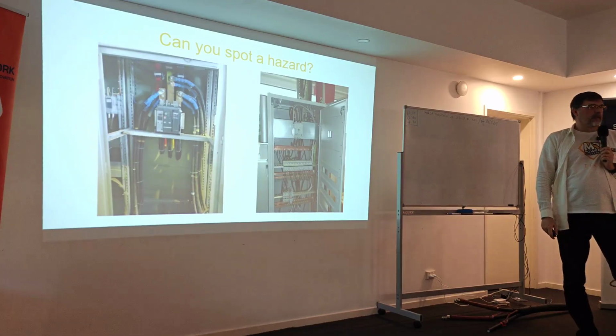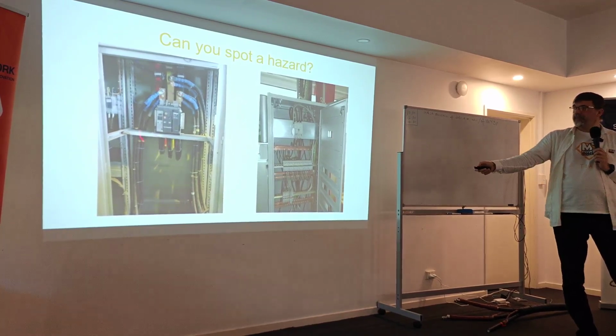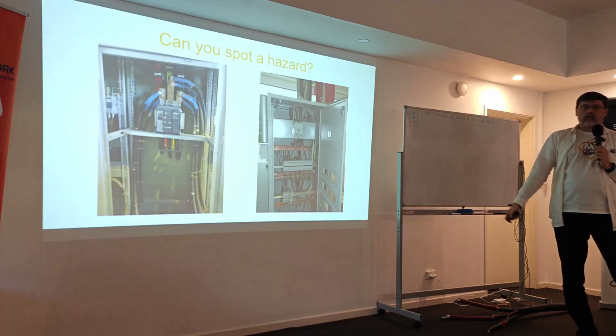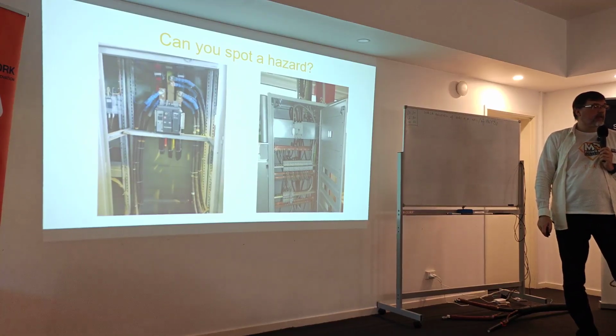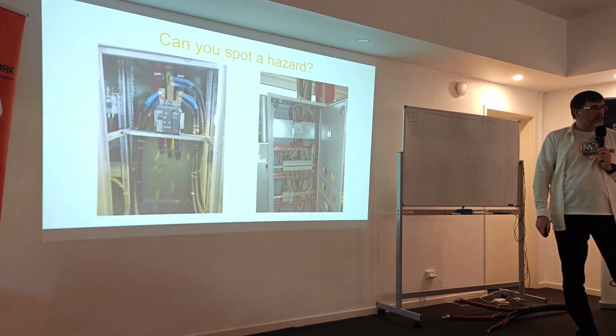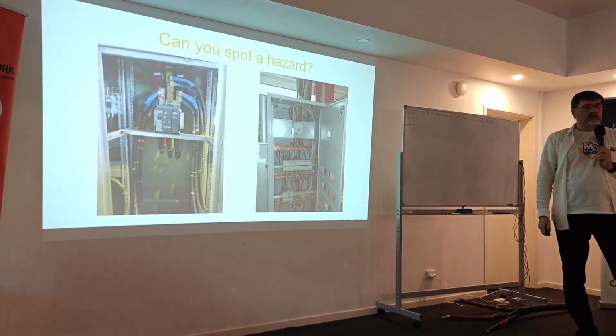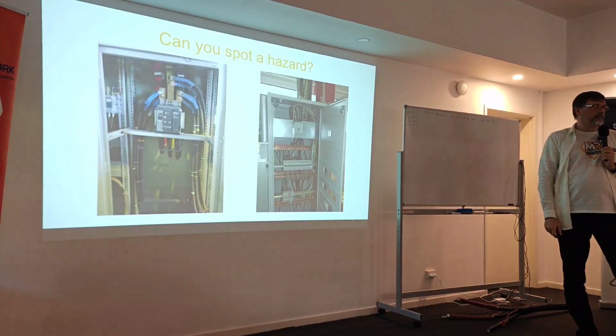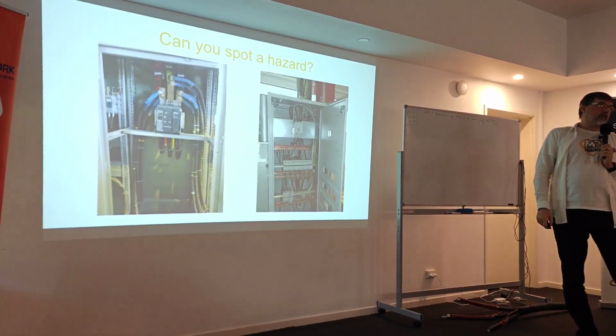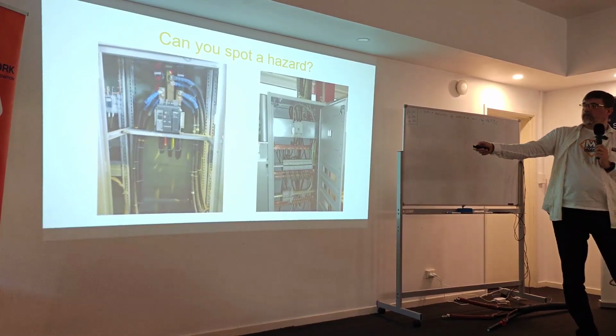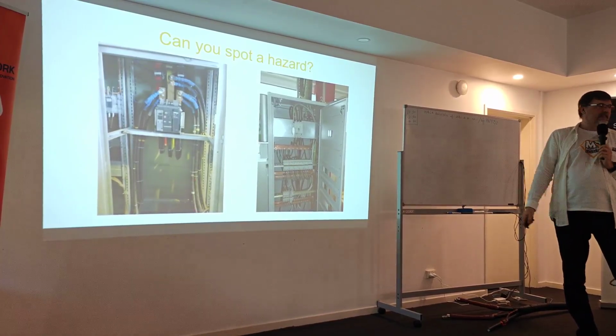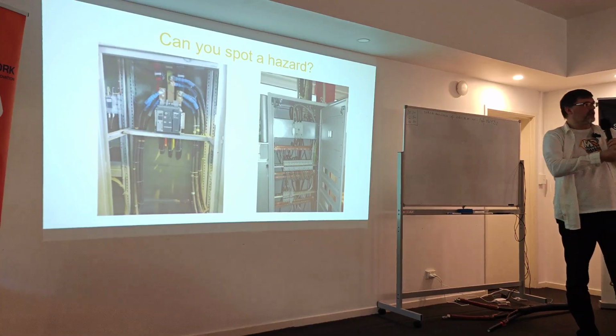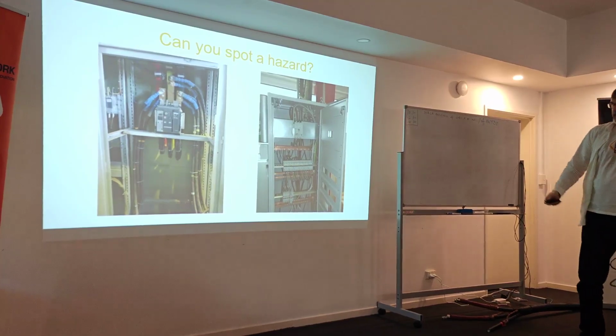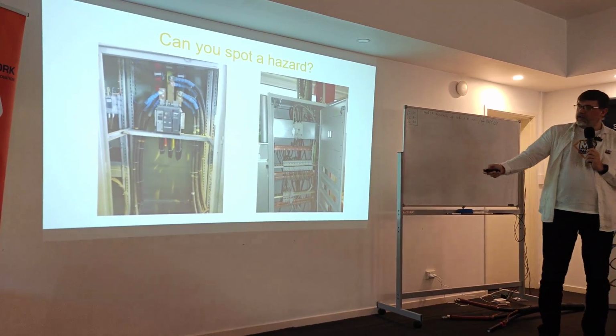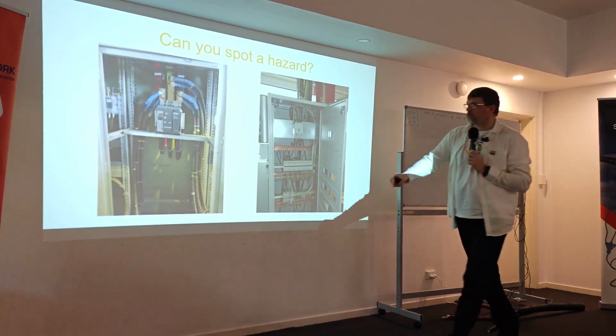Yeah, there's no IP screen. Okay, it's no covers, yeah? Let's say. I can tell you this is a bus section breaker that you have to operate, and to operate you have to open the doors. It's not visible from the outside. So that's how you operate it. If you've seen the video before on the Monday on the cables, then you can imagine the wire strap. This will not work. Once you have a short circuit, all of these things will just go all over the place. But also from a safety perspective, shock hazard, fun thing is, this is almost one-to-one size.